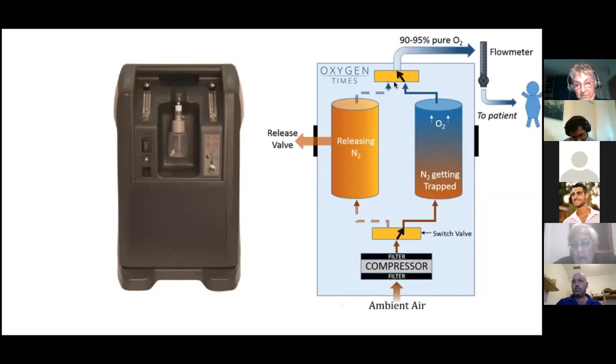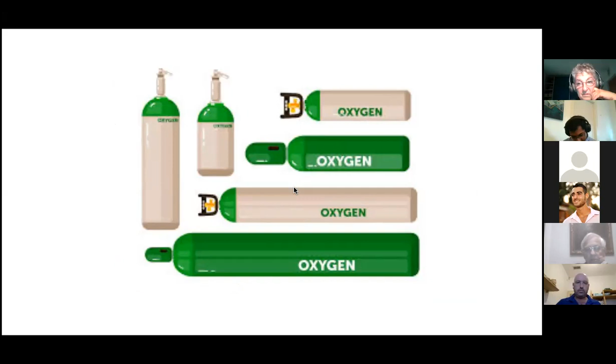It is a big advantage because we don't need to use oxygen tanks, which are consumable and high cost, and this machine can do it by itself. An important note about positioning the machine so that the oxygen generator can work properly is not to put it straight adjacent to the wall. It needs to be at least 30 centimeters away from the wall, and also in a ventilated room, so the air can go inside this filter properly, and the oxygen can be generated.